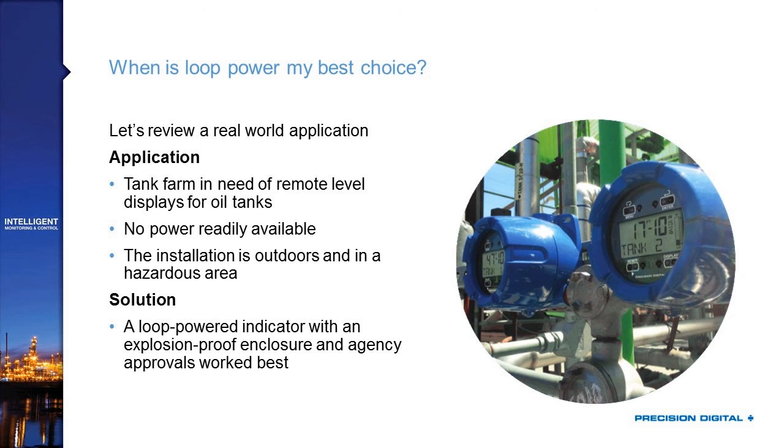The problem is the plant was already built. The tanks were already in, and power was not something that was being run through any of these conduit lines. The installation was also outdoors and in a hazardous area. So now if they do have to do a lot of rework, they're shutting down their plant. They need to make sure whatever they put in there is going to be sunlight readable. And if you add all of these concerns up, it turns into a tricky little application to solve for them.